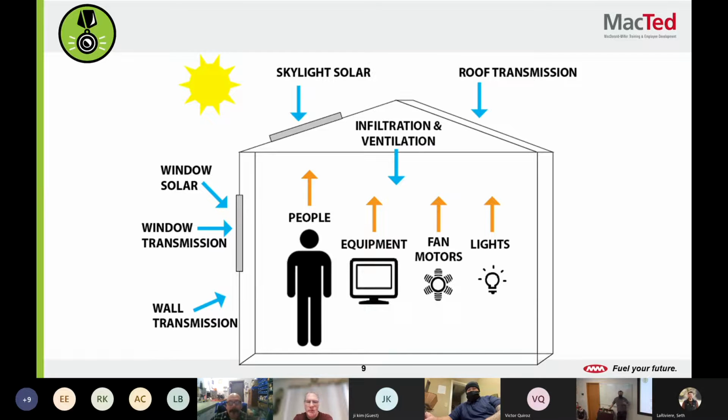It is generating heat within a space that our air conditioning systems have to overcome in order to maintain our temperature. What about outside? If it's really cold outside, is that going to make it harder to heat a space? What about cool a space? It's colder outside. Is that going to negatively affect our ability to cool a space? No. What if it's hot, like 115 degrees outside? Yeah. So that's what we call a heat load as well. It's just on the outside. Heat by nature likes to move from hot to cold. So if it's 115 degrees outside and we're trying to keep it 75 degrees inside our space, that heat wants in. And so when we talk about designing towards our extremes, that's something we have to account for.